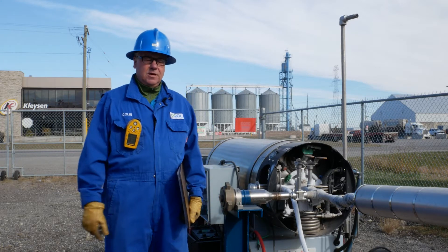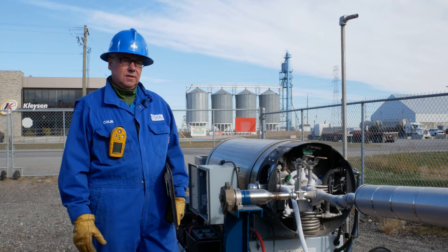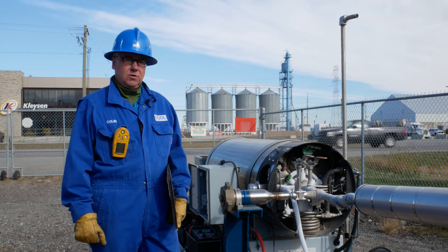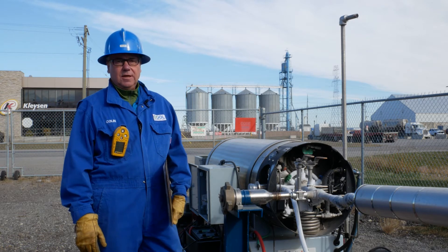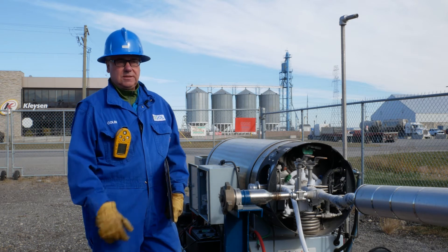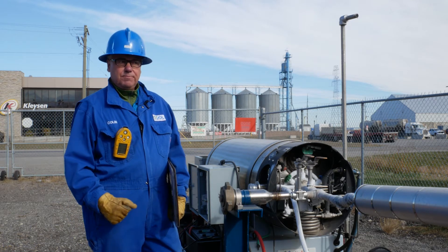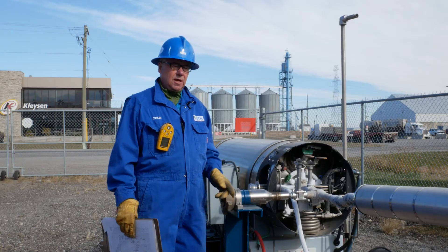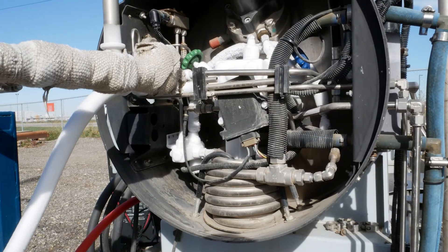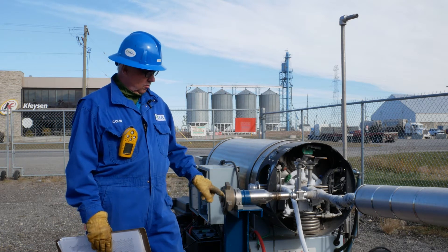What you're observing here is our LNG storage and vaporization system. It's really a fuel tank off of a class 8 truck, and for our pilot plant we have a closed loop methane system. So when we make LNG and flash through the JT valve, that LNG runs down into the storage tank. Because it's a closed loop, we have to re-vaporize the LNG that we make. So periodically you'll hear the tank — there's a pump that will pump the LNG up to pressure. That liquid is pressurized and goes through a heat exchanger, which is the coil you see on the end of the tank there.